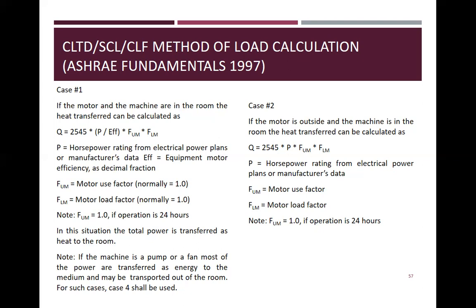Case 2. If the motor is outside and the machine is in the room, the heat transferred can be calculated as 2545 times P times FUM times FLM. P is the horsepower rating from electrical power plans or manufacturer's data. It's the same. FUM is the motor use factor. FLM is equal to the motor load factor. FUM is 1.0 if operation is 24 hours.